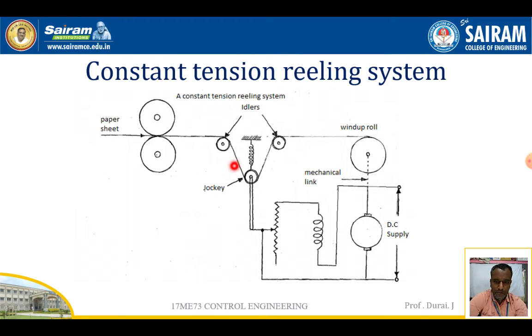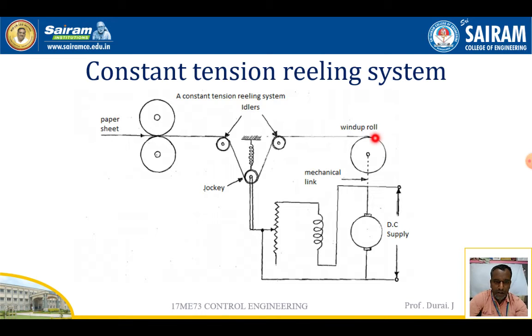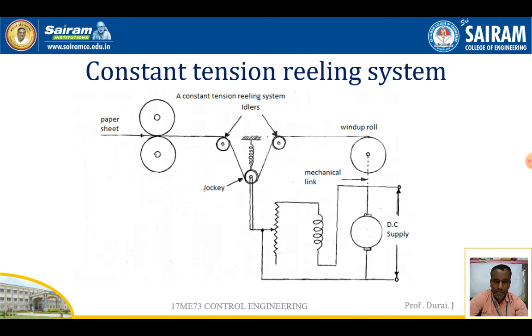When the paper's tension increases, the jockey moves upward, which changes the field current. Due to that change, the speed of the roller is reduced or increased according to the specific requirement. When the jockey moves upward, tension is increased; when the jockey moves downward, tension is decreased. According to that, the rotation of the roller is controlled.